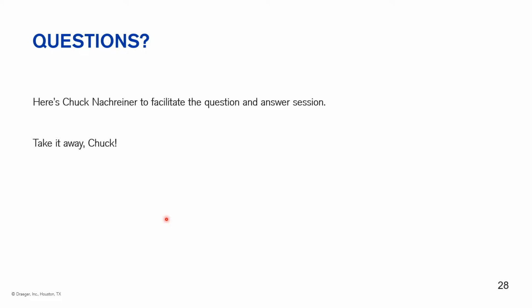Okay. One from Kevin. Please explain sensor poisoning. Also, what will happen if it is exposed to 10 or 15 times concentration? Again, I touched on poisoning earlier, but a lot of our sensors, CO sensors, H2S sensors, if they get hit with high concentrations of gas, it may take a few minutes for that sensor to recover once it's brought out to clean air. But we fully expect those sensors to recover and still be working sensors even after those high concentrations.